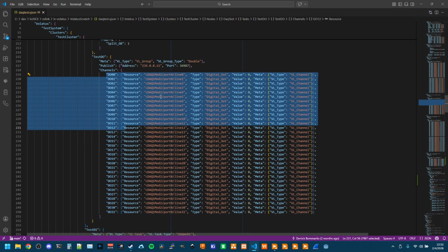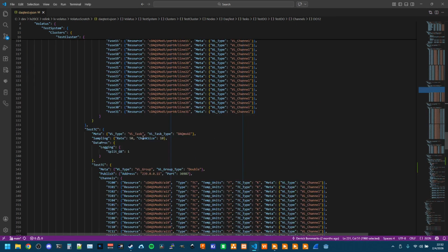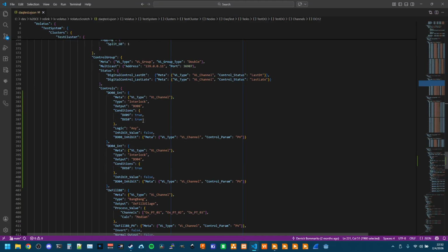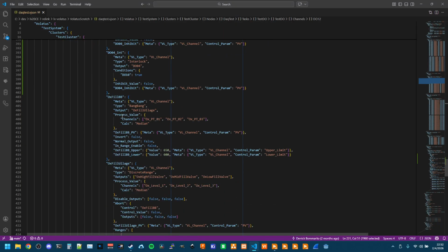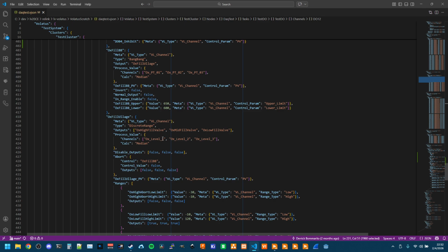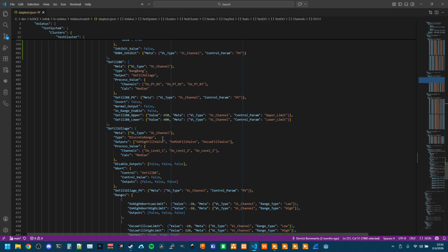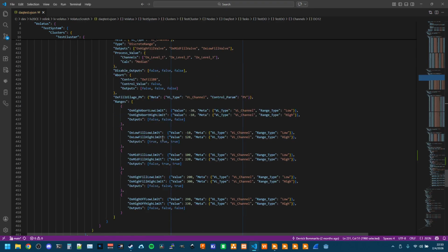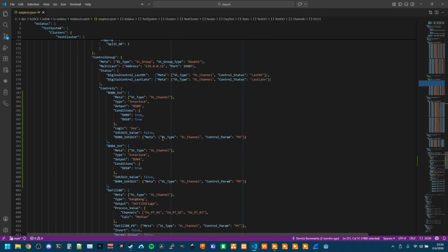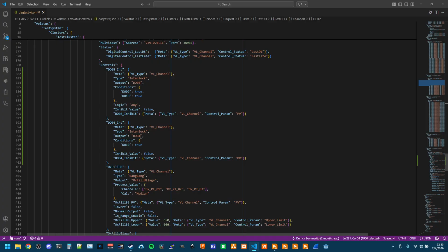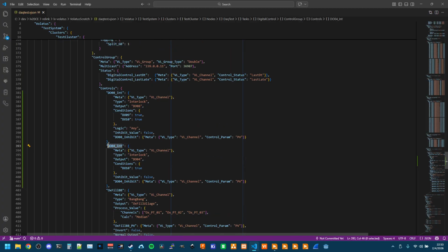I'm still using the simulated cDAQ chassis in Max and DAQmx for most of this simulated I/O functionality. So I just have a bunch of digital output named channels. And then the digital control, which has been what supplied the bang-bang discrete control for ullage, heater PWM, valve timing, all sorts of different digital control capabilities, is now where this interlock behavior lives.